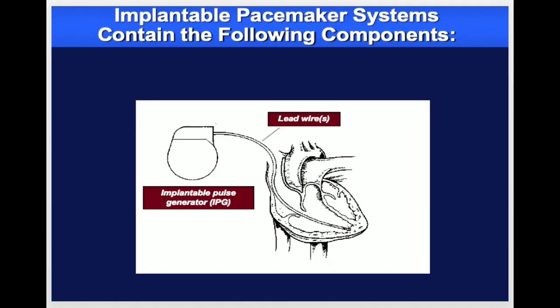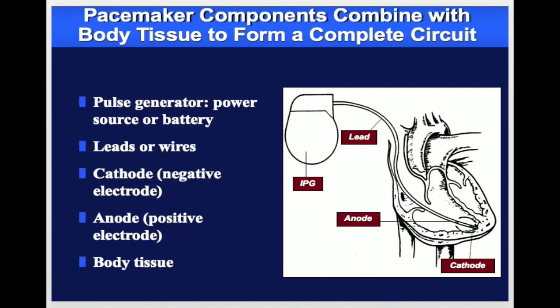The leads consist of electrodes at the distal tip. These electrodes are conductors located at the end of the lead. They deliver the electrical impulse and pick up the signals from the heart to the pulse generator. This will be used as sensed electrical activity for the pacemaker.